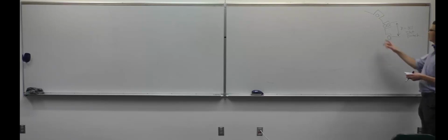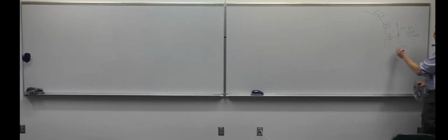So if we look at the winding where we had one slot shorting, then we're actually going to get a reduction in the induced voltage, because unlike if the phase or the set of coils was overlapping like this, when we shift one coil relative to the other, we're going to create a phase shift in the induced voltages, and so that reduces the magnitude of the voltage.